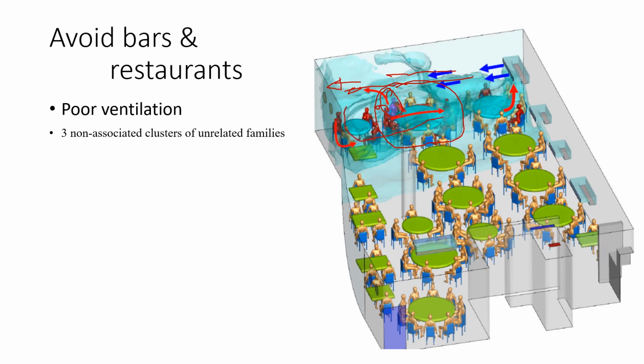And because this system is recirculating, the air goes backwards, and these 2 are also infected. Therefore, this kind of room recirculating system is very poor. It's very risky, and you should avoid this. And recently, because of new regulation, CDC advises that restaurants and bars need to have 100% fresh air, not recirculating.